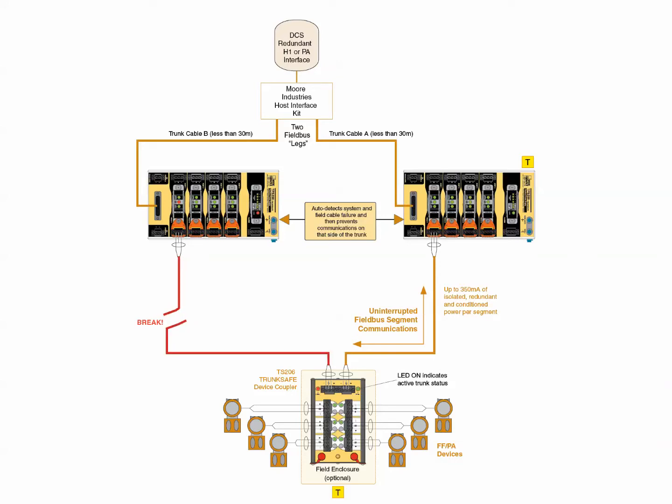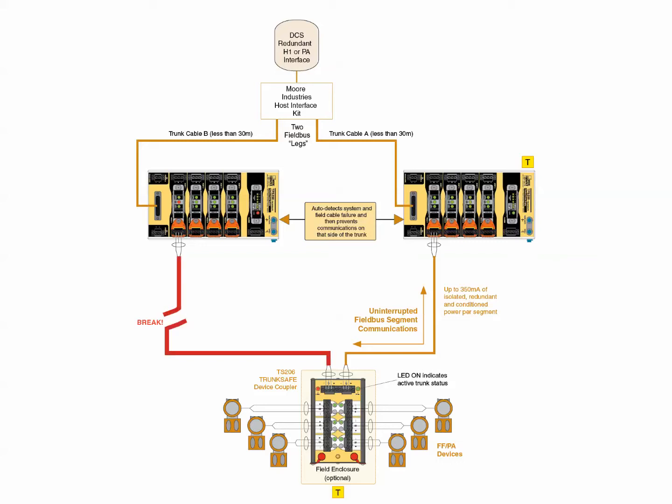When a trunk fault is detected, Trunk Safe's device coupler detects the fault and engages its patented auto-termination feature. Internal blocking circuitry also prevents a short circuit on one leg from affecting the other leg.